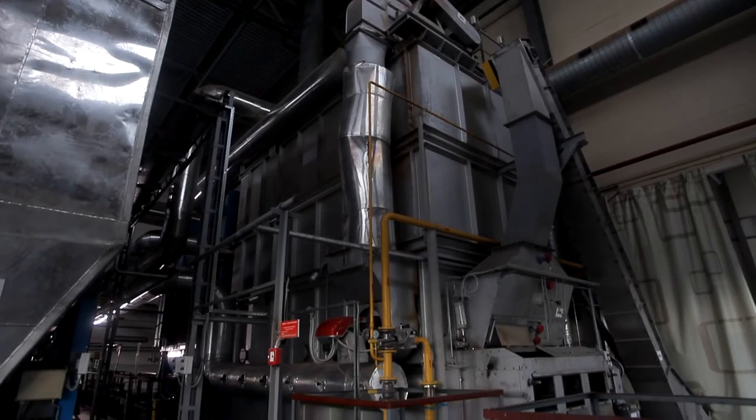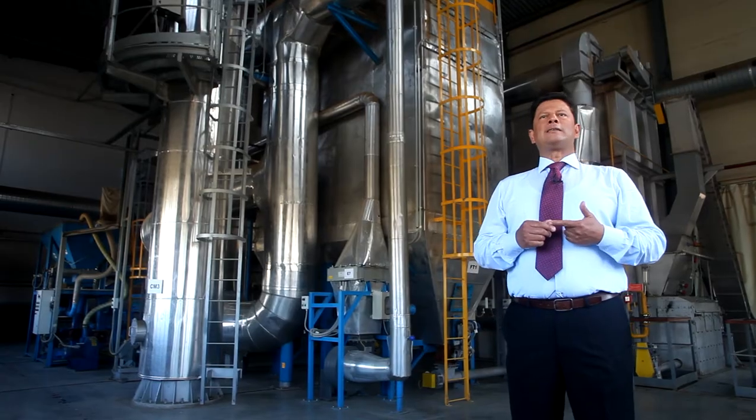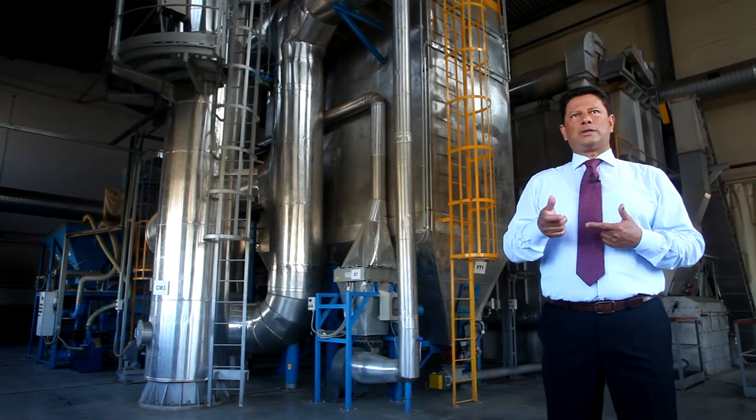During the combustion of pellets, quite a large quantity of heat is released, but not all the heat goes to support the technical process — there is a surplus of heat. We are now planning to use this surplus to heat our enterprise during winter. The surplus of thermal energy may also be used for electricity production. Additionally, we could recover 60% of the heat used in the drying process, making hot water which could be used for heating urban and industrial facilities.